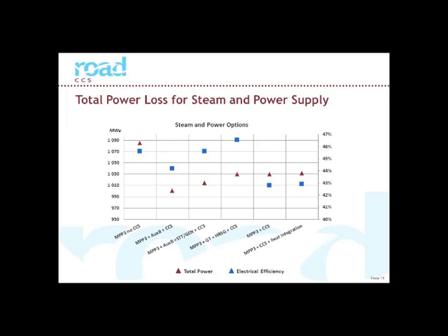Then to the right, the 3 options with external boilers for a steam supply. The 5th option is extraction of steam from MPP3, and at the most right side also the steam extraction from MPP3, but also with some heat integration. I will come to that later. The last option was the preferred option, although it leads to a reduced power output of MPP3. But we have chosen this option because it has the lowest capital expenditure, the highest efficiency, and it is the least complex one because we don't have to build any extra boilers.